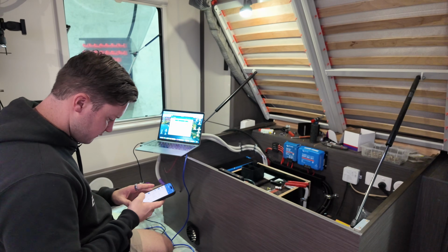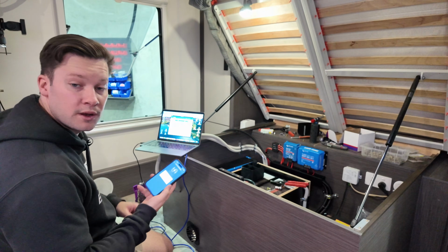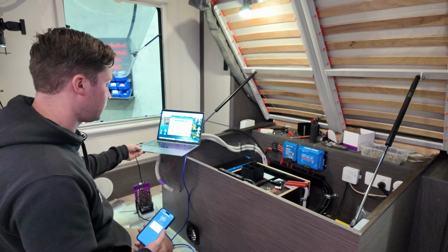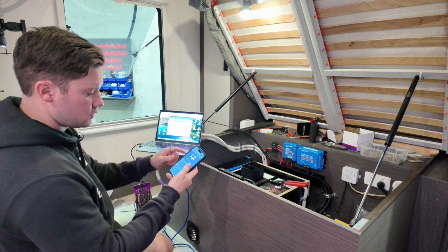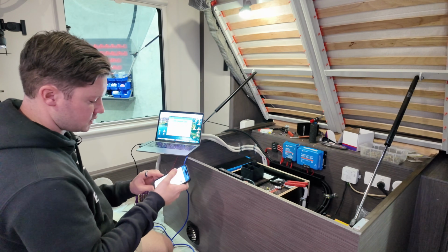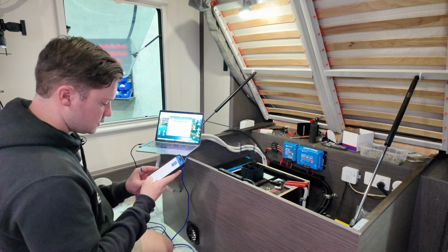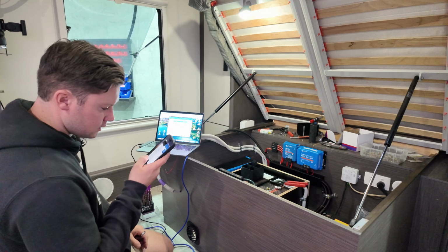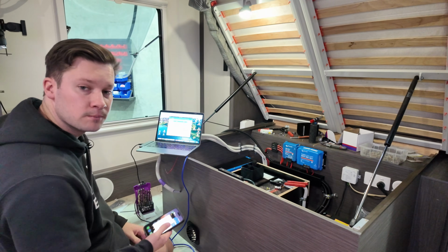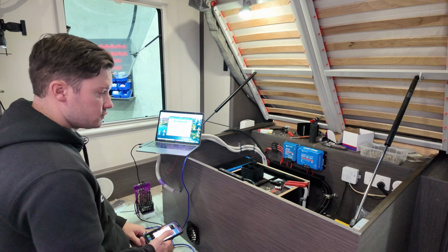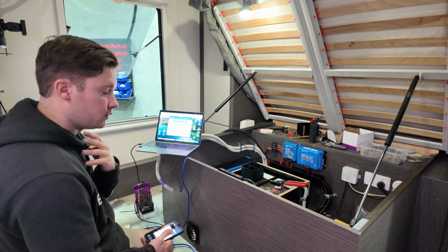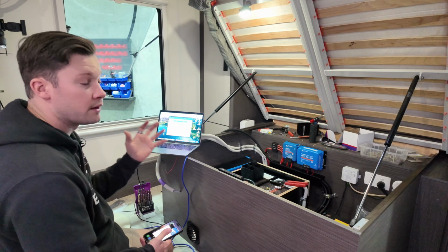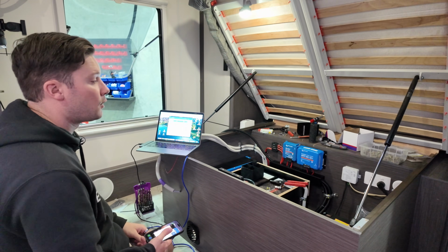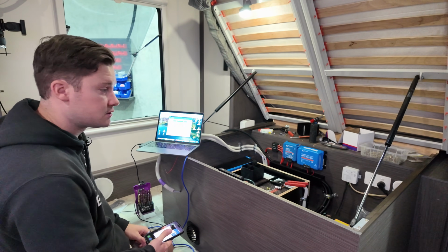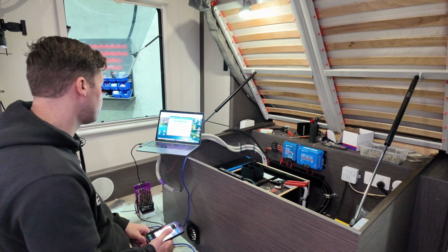Put another circuit breaker in for the multi-plus. The boys are just having some lunch, so what I'm doing now is going through and programming everything. I've just done the solar controller, and now I'm doing the Orion XS, the 50 amp DC charger, doing things like programming them to lithium, changing the pin code so that the pin codes are all relative to us at JT and the same across the whole system. That way I know no one's touched it since we programmed it, if they do ever run into issues.